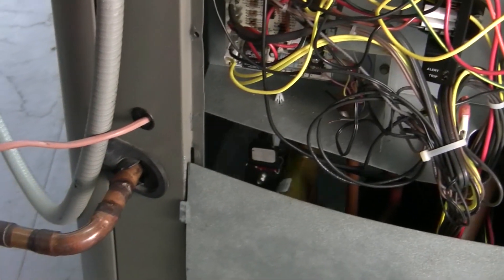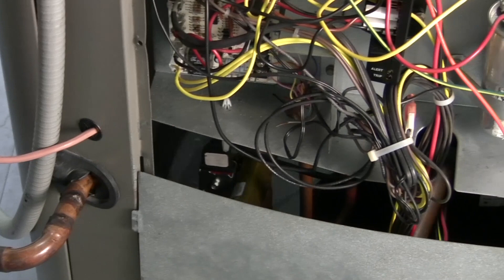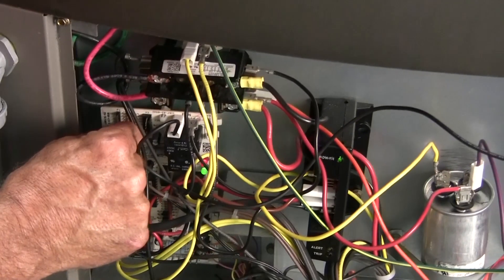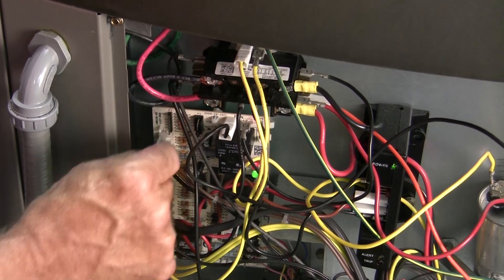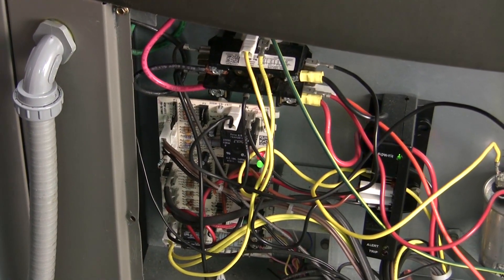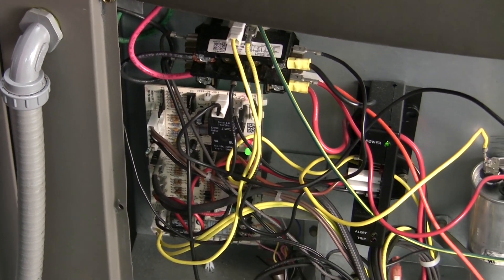We are now in heating, so it is in defrost mode. We know that the board is good. Now we can allow that to run, or we can hit the test again and it will shift back into heating. That's all there is to it to test the demand defrost board.